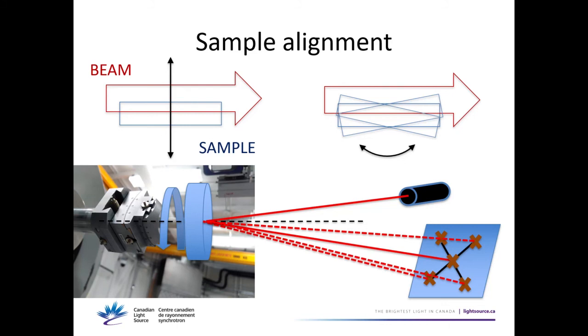To achieve that, we shine a laser on the surface of the sample and rotate phi, marking on a wall the laser reflection spots every 90 degrees. Usually the spots are all crooked when we start, with separate spots on the wall. We adjust the arcs in the goniometric head to make those spots as close as possible. When that's done, a phi rotation of the diffractometer coincides with the sample normal and the spots stay put — no crooked motion that would kill the single crystal alignment.